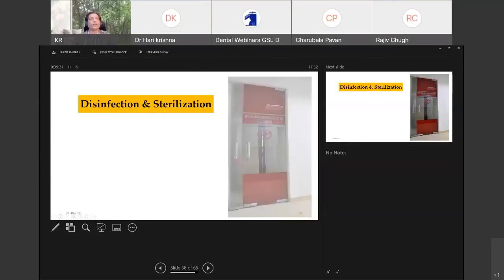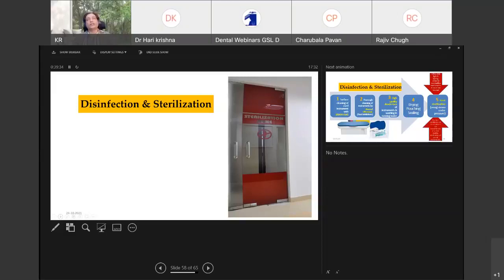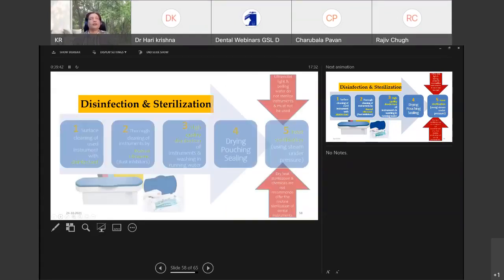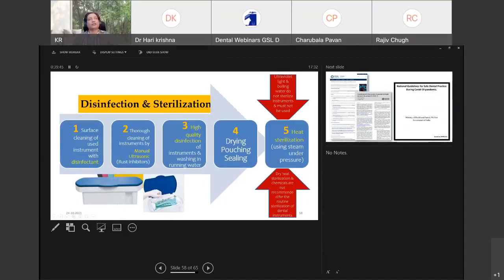So coming to disinfection and sterilization, if possible, please have a sterilization zone in your practice, wherein you can clean everything properly. The first part is that the surface has to be thoroughly cleaned, and used instruments cleaned with disinfectant, and then thorough cleaning of instruments by manual or ultrasonic methods with rust inhibitors, and then high quality disinfection of instruments and washing in running water, then drying, pouching, and sealing. And then comes heat sterilization using steam under pressure, for example, your autoclaves.